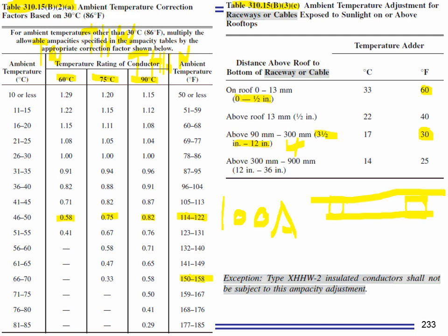So look what happened to your cables. Now you lost almost half of the amps in any cable that you use there. Any cable. Even the best cable, say if you're going to use THHW-2, which is rated for wet location, that gives you 90 degree in both wet and dry, you still lost almost half of the ampacity.